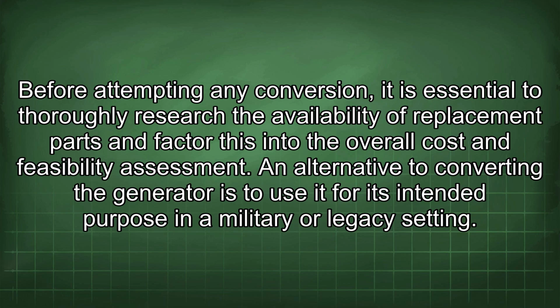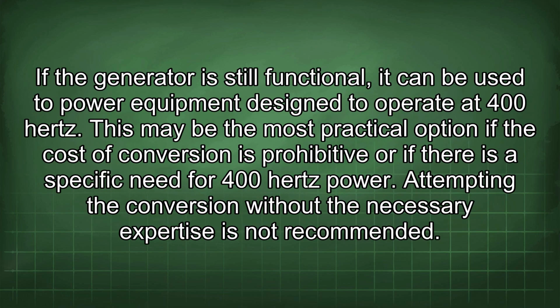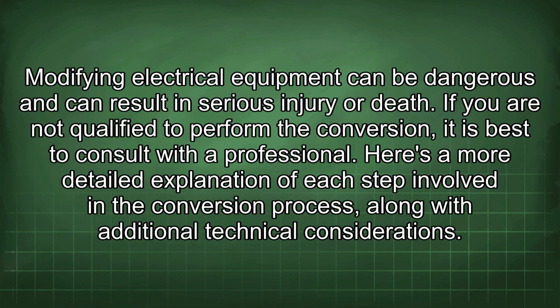An alternative to converting the generator is to use it for its intended purpose in a military or legacy setting. If the generator is still functional, it can be used to power equipment designed to operate at 400 Hz. This may be the most practical option if the cost of conversion is prohibitive or if there is a specific need for 400 Hz power. Attempting the conversion without the necessary expertise is not recommended. Modifying electrical equipment can be dangerous and can result in serious injury or death. If you are not qualified to perform the conversion, it is best to consult with a professional.